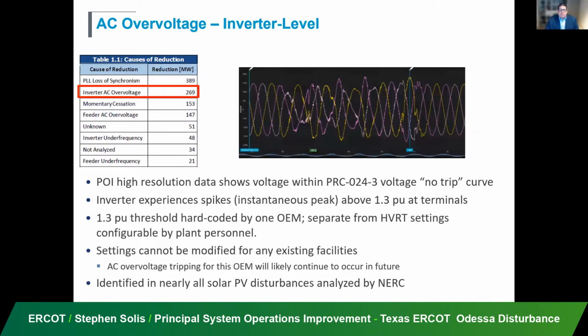When we look at overvoltage, one thing that's really important to understand is that we have rules, and those rules say there's a no trip zone. So when voltage at the point of interconnection is within a particular range, your inverter-based resource should not trip off. What we were seeing is that at the terminal of the inverter, they were seeing voltages much higher than what was actually seen at the point of interconnection or on the system. So you have your inverter terminals, you have your feeder system, you step up past your transformer, and then you have your point of interconnection, or perhaps even a remote bus away. At the terminal, they're seeing these higher voltages and tripping off at the inverter level while the system remains within the zone.